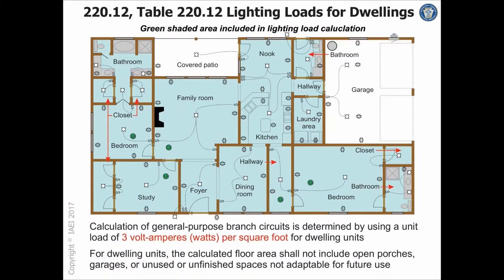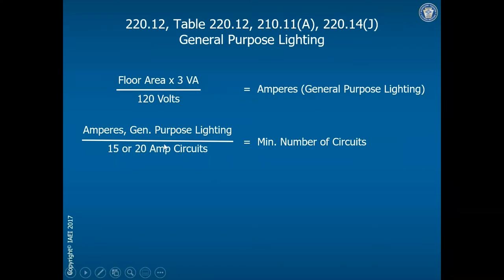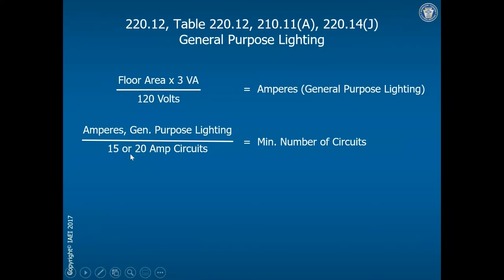Based on 3 watts per square foot, we find the floor area and multiply it by 3 volt-amps per square foot. Then we divide that by the actual voltage — those general lighting circuits are rated at 120 volts. Floor area times 3 watts divided by voltage gives you an amperage rating for your general lighting load. Then you take the actual rating of the branch circuit — the overcurrent device protecting that circuit — and divide it into that amperage value to get the minimum number of general lighting branch circuits required.